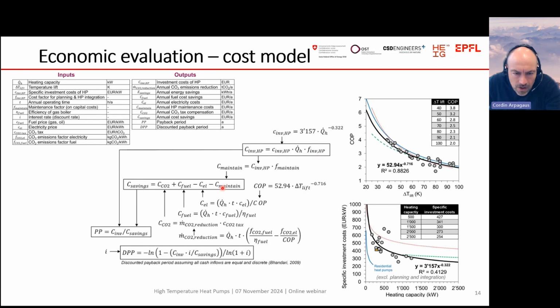We need information on maintenance cost, installation factor, and planning. Then we need information from the application, the temperature lift, which gives the COP or efficiency. It needs to be a meaningful temperature lift which gives a certain efficiency, because it goes directly into the operating costs or electricity costs. So there we have the operating time, the electricity costs, and the capacity of the heat pump. That is very important - the size of the heat pump, the heating capacity.